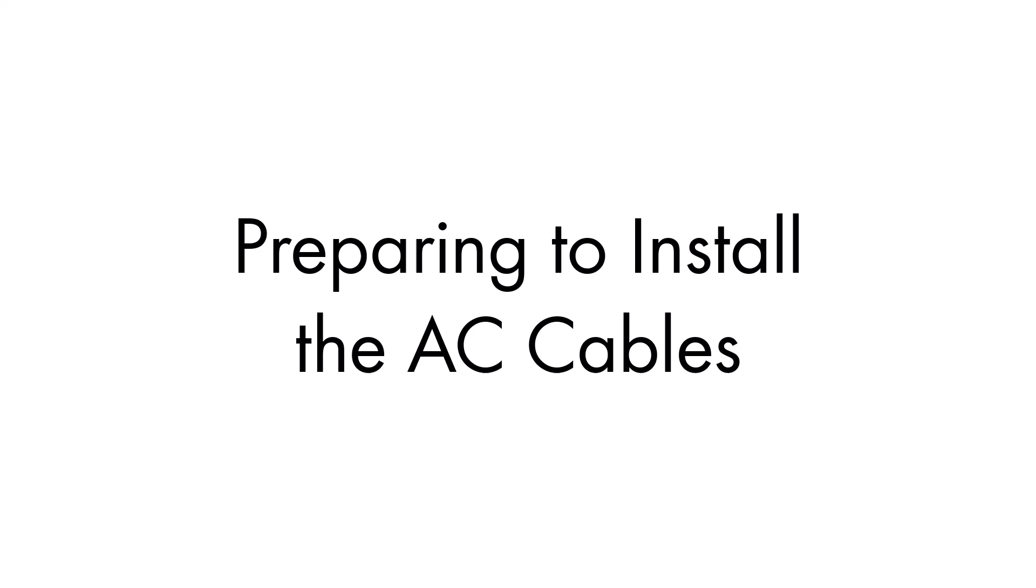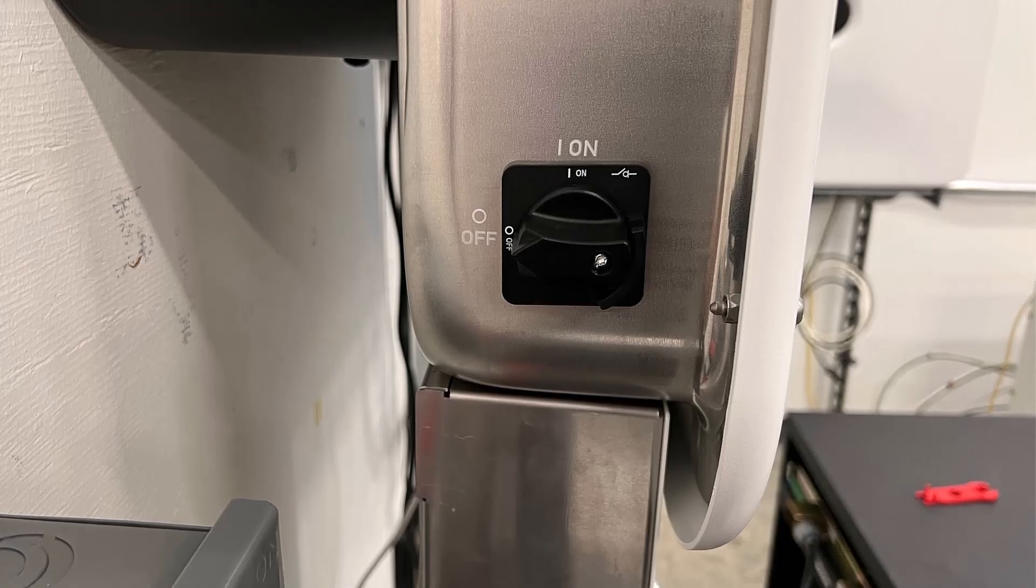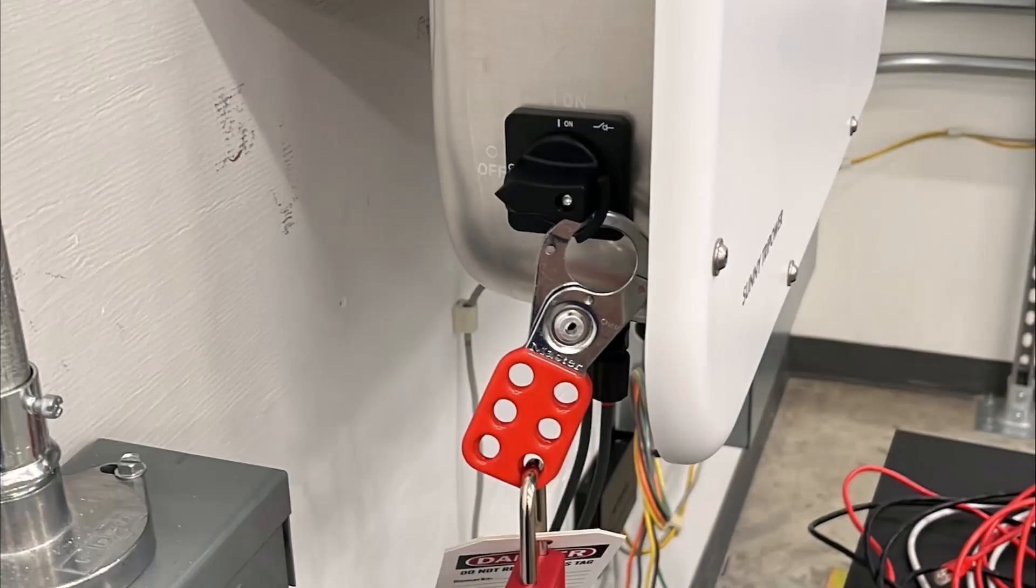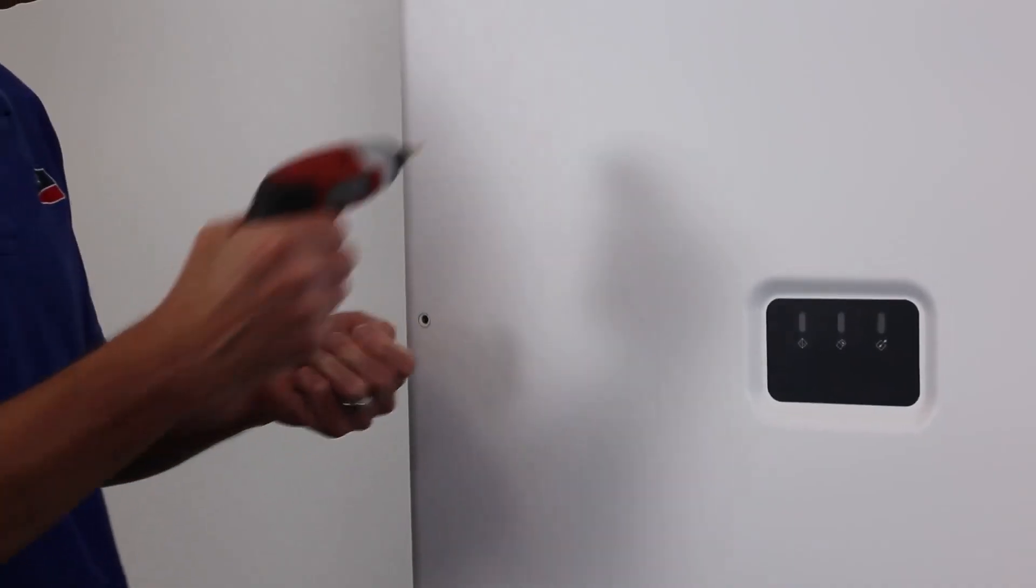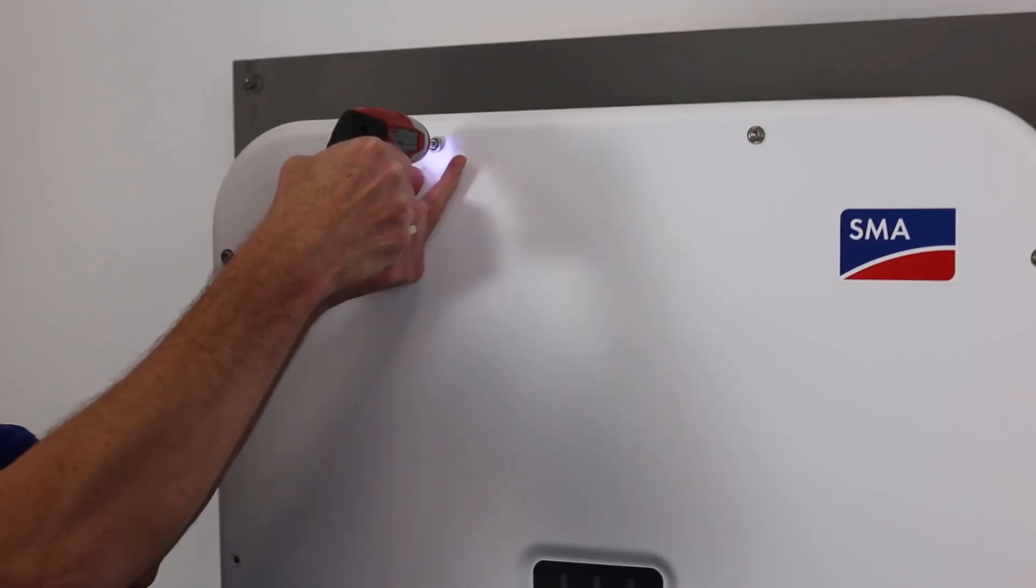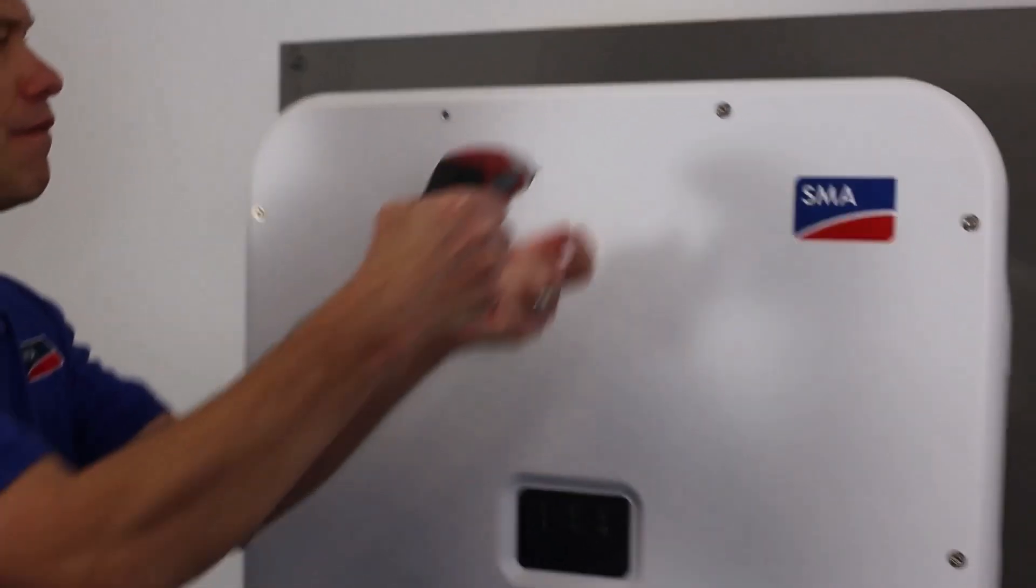Let's go through the steps to connect the AC terminal cables. Begin by ensuring the DC disconnect is in the off position. If you're using a lockout-tagout lock, please attach it now. Gently remove the inverter front cover by unscrewing the 10 Torx 25 screws. Set the lid and screws aside and look inside the inverter.